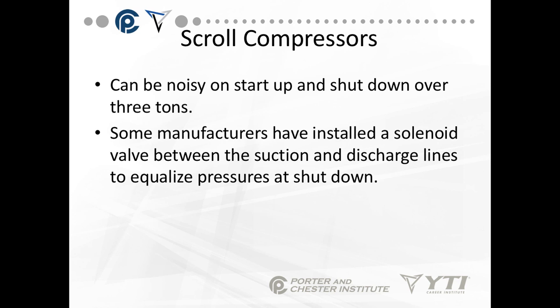The scroll compressor can be noisy on startup and shutdown when it gets over three tons. The larger units, especially on air conditioning systems — the older scroll compressors were noisy. Some manufacturers have installed a solenoid valve between the suction and discharge lines to equalize the pressure, which counteracts the noise.